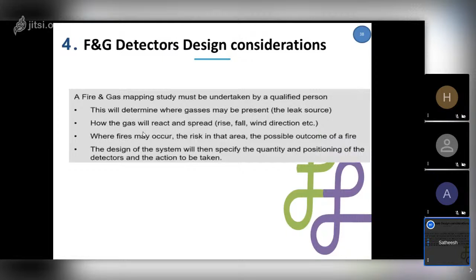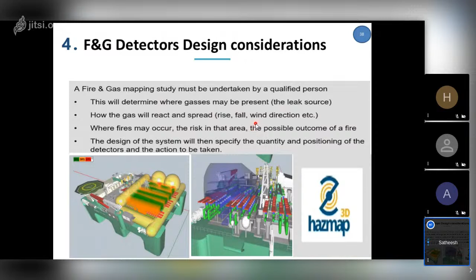So now, design consideration. What we really need to look at is where the gas will be present and how much, and where we need to position our gas detectors. In the past we used to do the engineering manually. Now we have nice 3D modeling software, so literally we can visualize the plant exactly, and we position the gas detectors and it will show the green ones as the coverage of the gas detectors, whereas the red ones are not covered. That way we have full control on whether it is covering the complete plant.